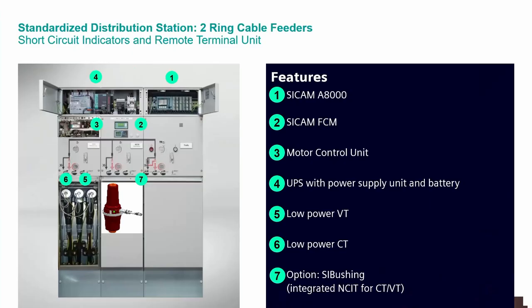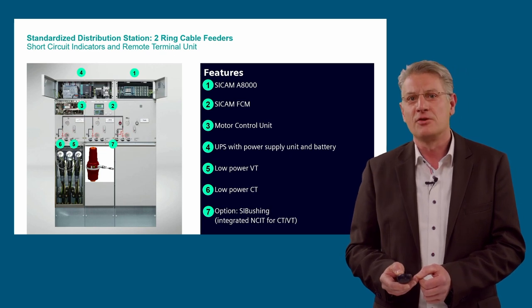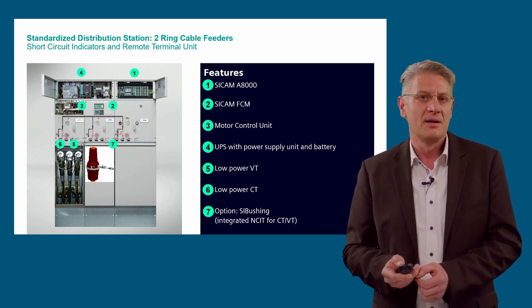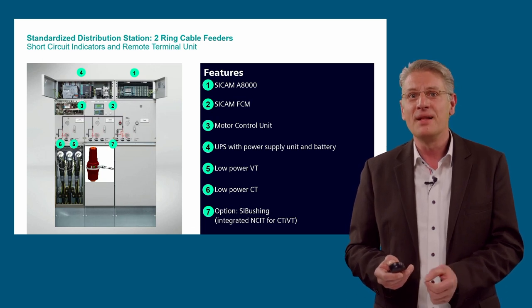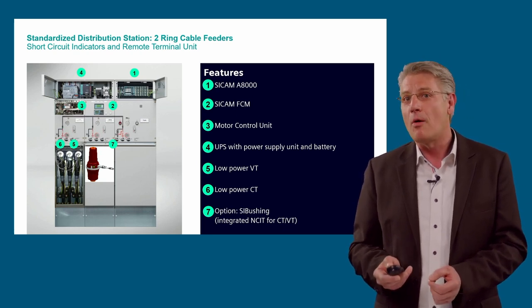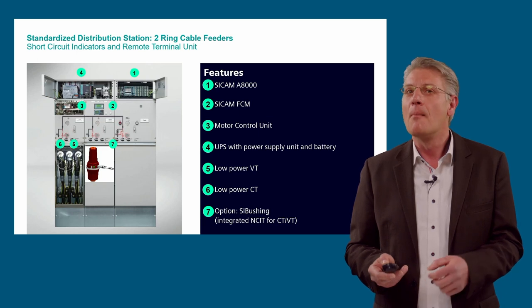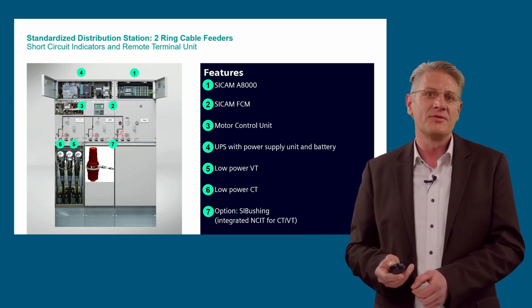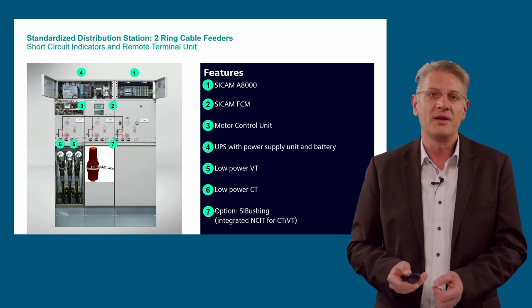The standardized station has two ring cable feeders with short circuit indicators and remote terminal units. The switchgear is a Siemens 8DJH ring main unit, which includes additional components: a SICAM A8000 as remote terminal unit, a SICAM FCM per cable bay as feeder condition monitor, a motor control unit for the built-in motor drive, a UPS (uninterruptible power supply) with battery, low power CTs (current measurement sensors), and low power VTs (voltage measurement sensors). In future, both CT and VT sensors will be integrated as an option in the SIBushing. All substations of the project have a similar approach and include a high level of integration of electrification and automation.